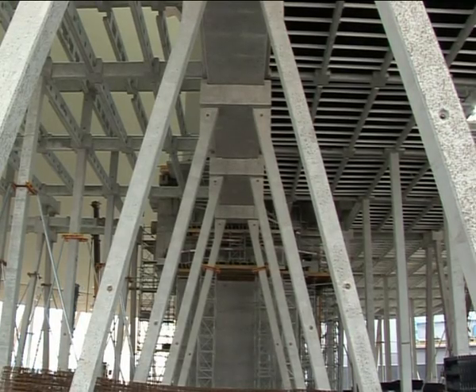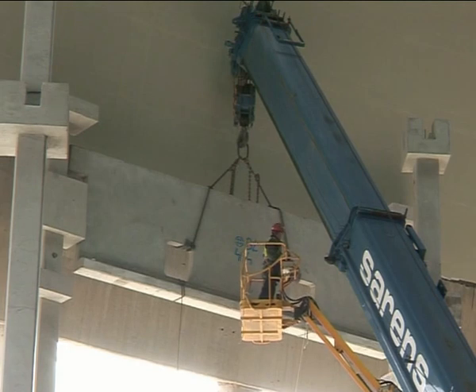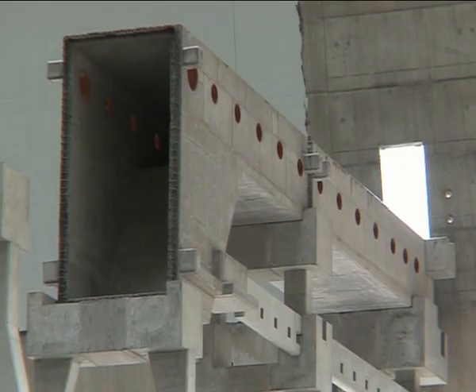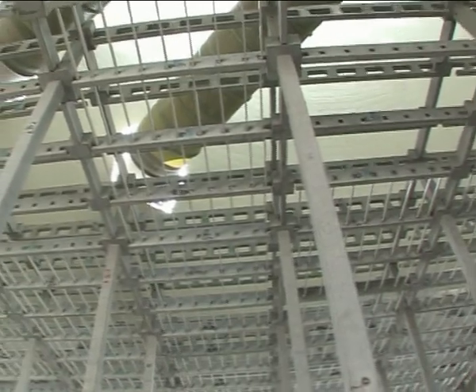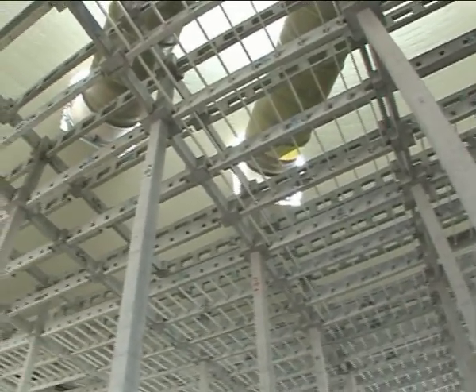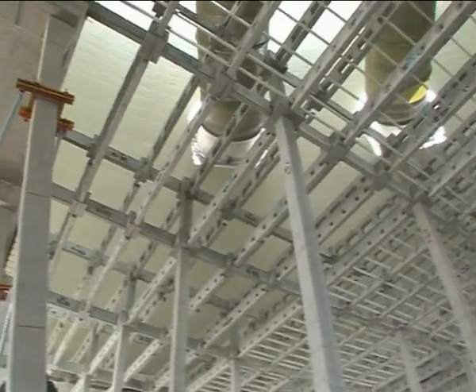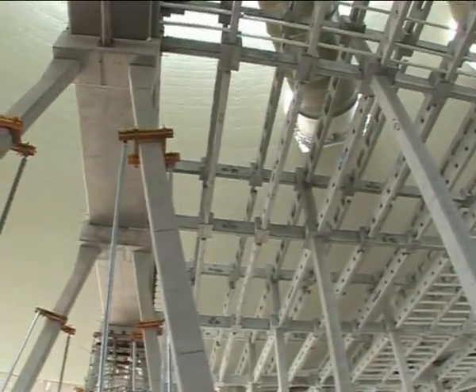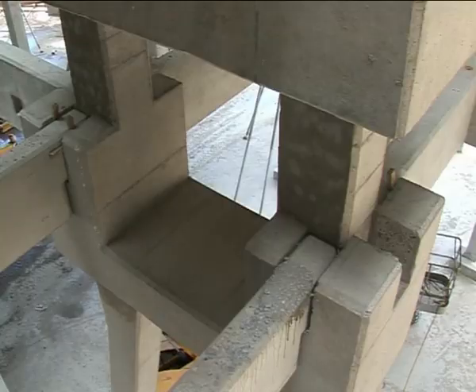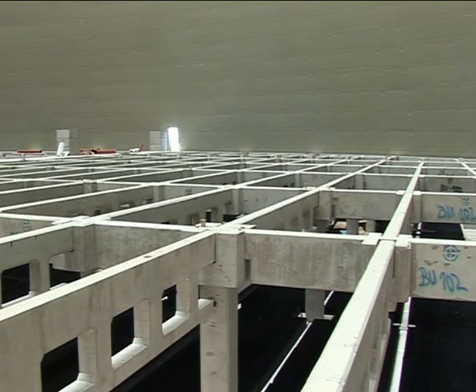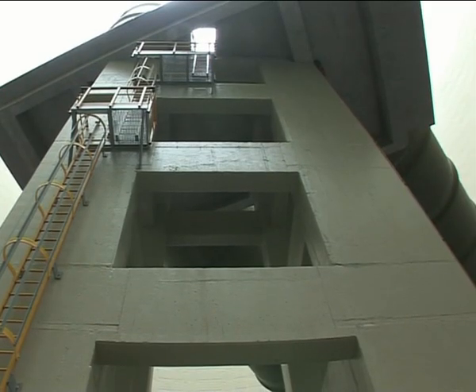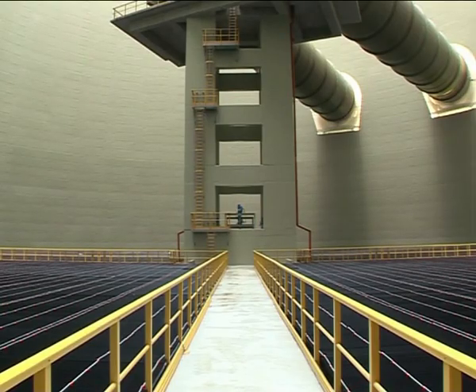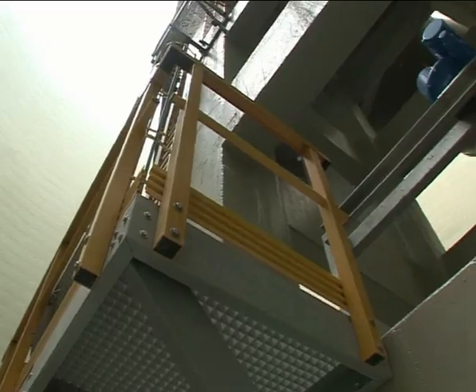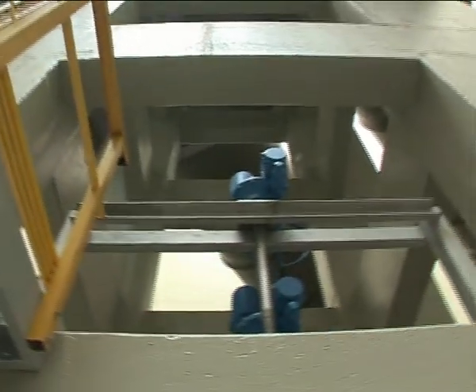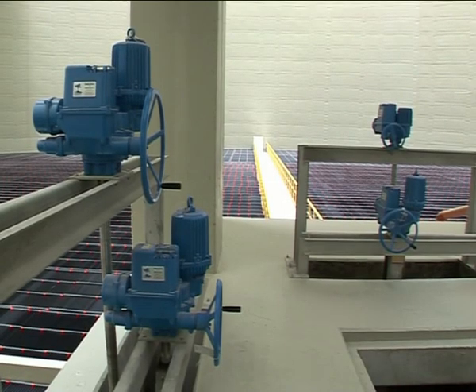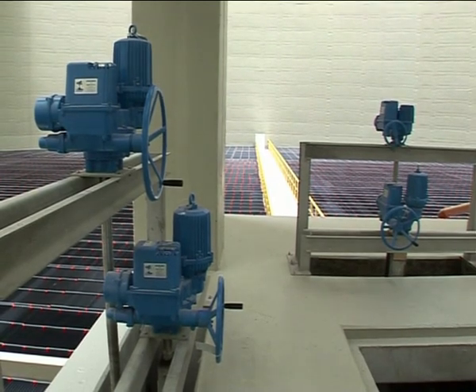The supporting structure was designed and constructed as precast beams, columns and pipes. 220 columns, 1,336 beams and 28 different ducts were built into the cooling tower. About 3,500 cubic metres of concrete were used for the prefabrication of these elements. In a central location, we constructed a duct to carry water up from -7 to +11 metres. There, the water divides into 4 main ducts supplying different sections of the entire cooling system.